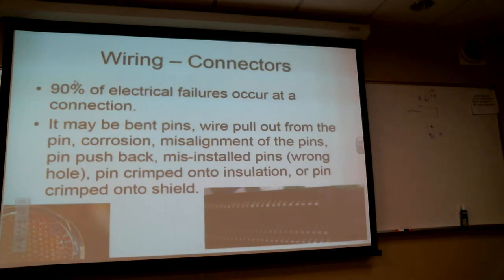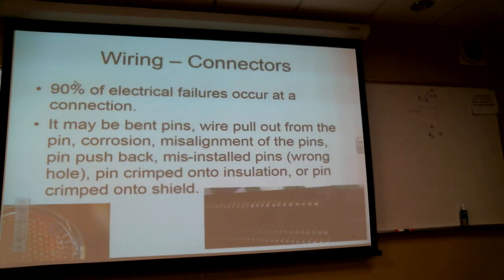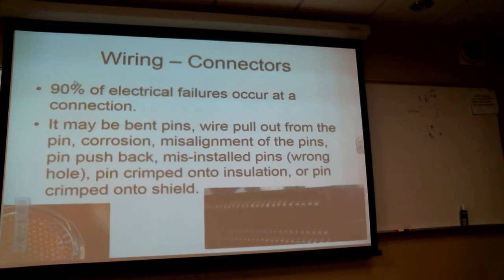With respect to wires themselves, I've only had two occasions — excluding mechanical damage like someone drilling through the wiring — where the wire itself failed from the inside. In both cases, when I split the wire insulation open, it looked like things got too tight and some strands broke. Otherwise, almost always the problem is at the end of the wire.